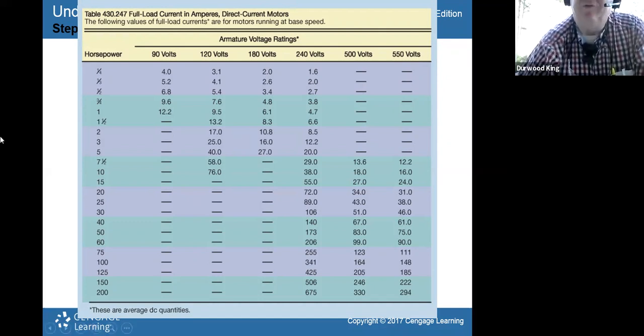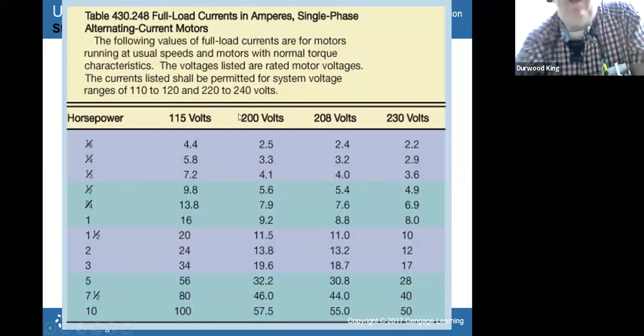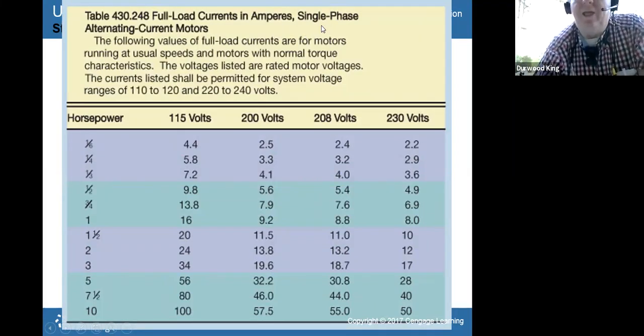Let's see, where's my mouse at? So if you had a DC motor, for instance, if it was a 5-horse motor running at 120 volts, it would draw 40 amps. So this is the amp ratings in here. A 10-horse would draw this, but at 240, it would draw half that. Okay. The next chart is for single phase AC motors, alternating current motors.